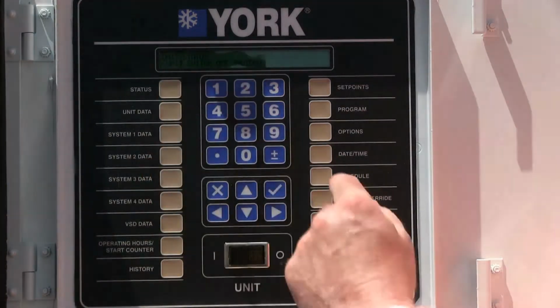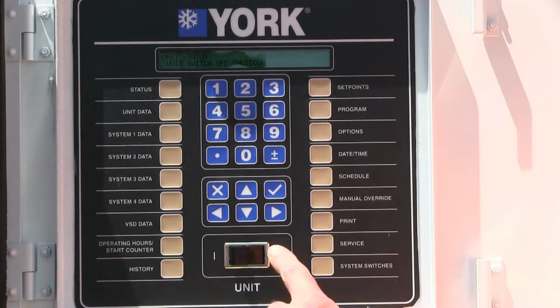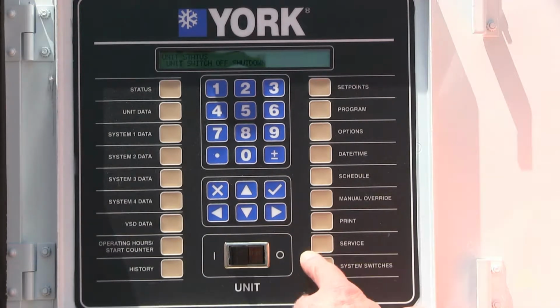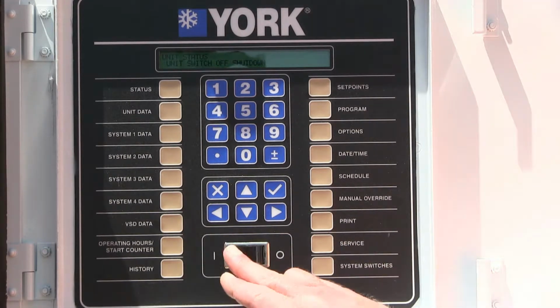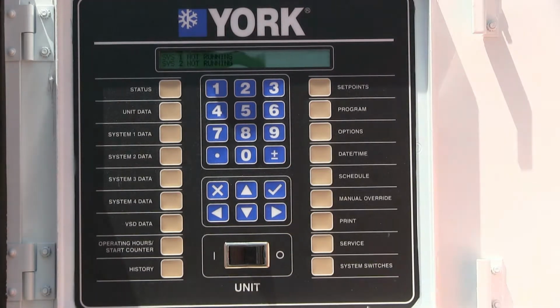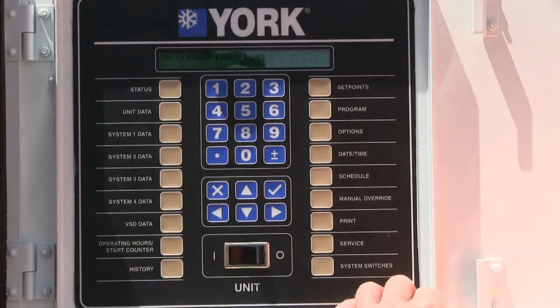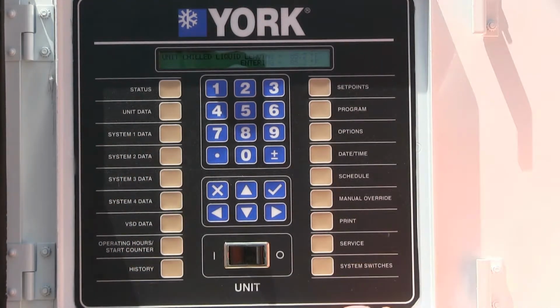Now watch when I go back to my screen, I'm still off on my unit switch, but now I'm not off of the system switch. So we're going to start the machine up now, and that's just as simple as turning the switch on there. And our status is going to say that our variable speed drive DC bus is pre-charging on circuit 1. The left-hand side is circuit 1, right-hand is circuit 2. It's getting ready to start the circuit 1 compressor. It'll take maybe about 20 seconds. It'll start up. And while we're looking at that, we can go back to our unit data and notice we're still running 85 degree water.